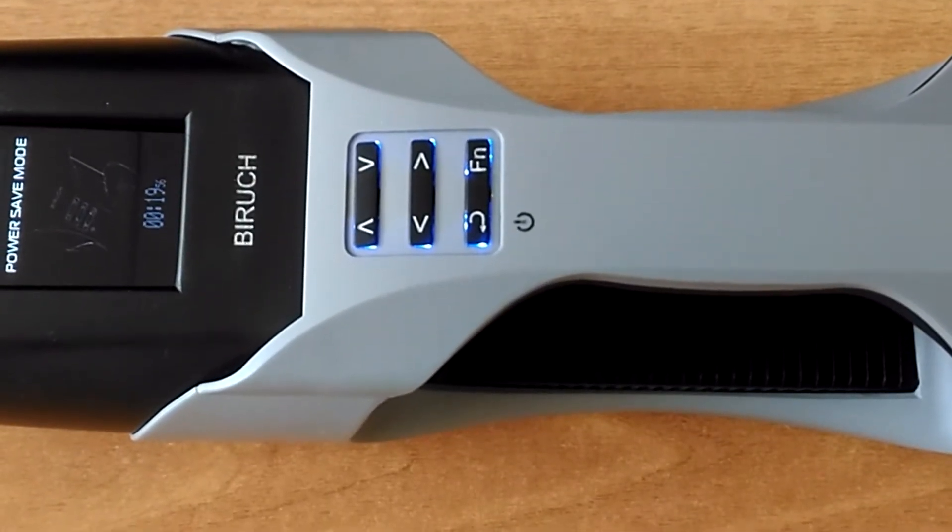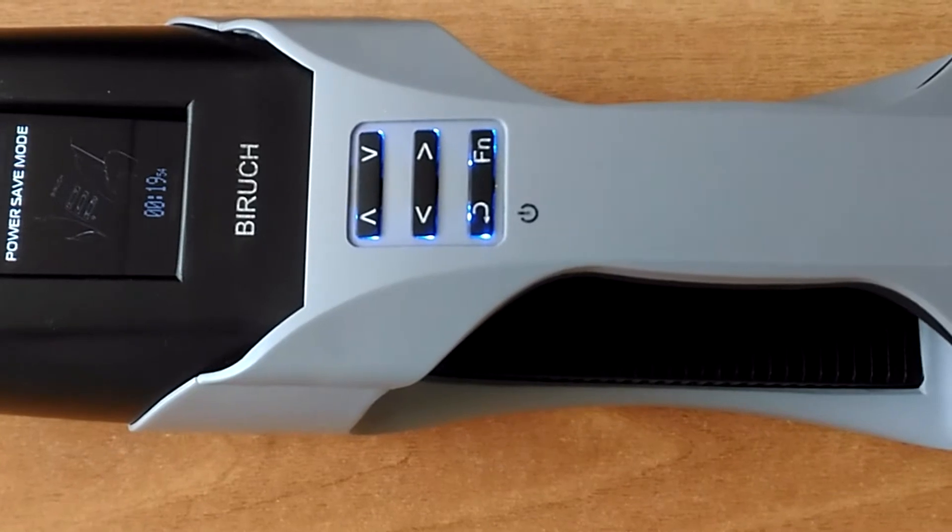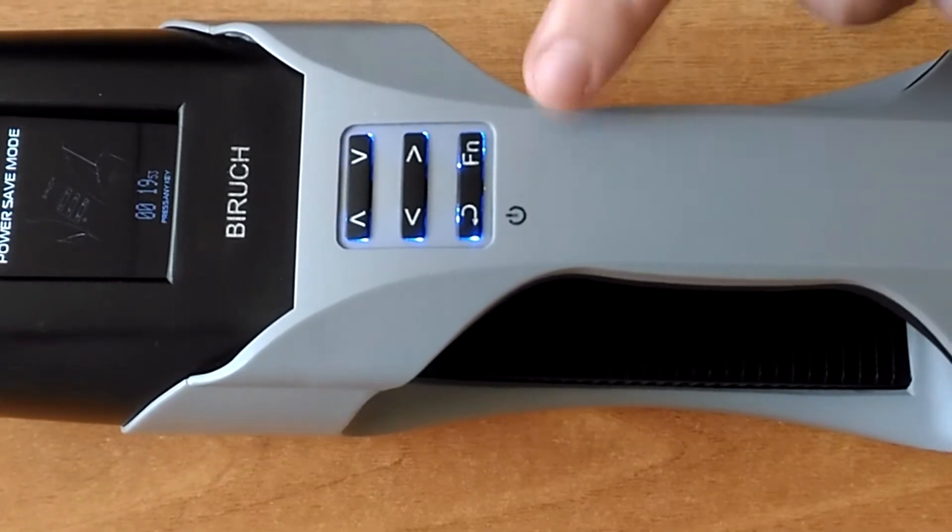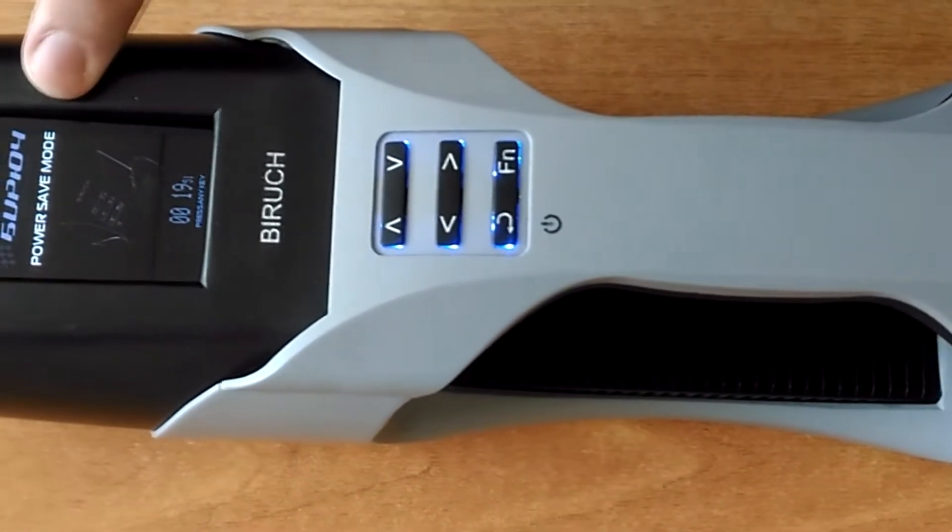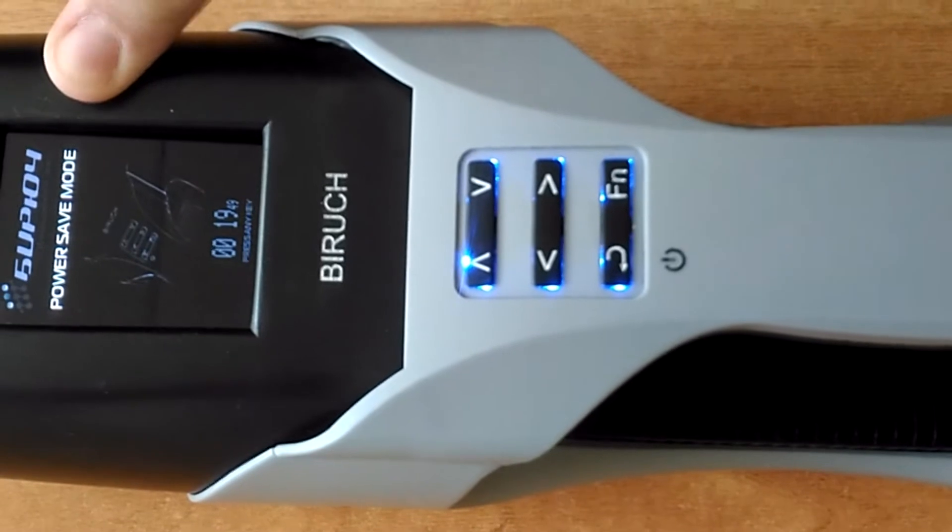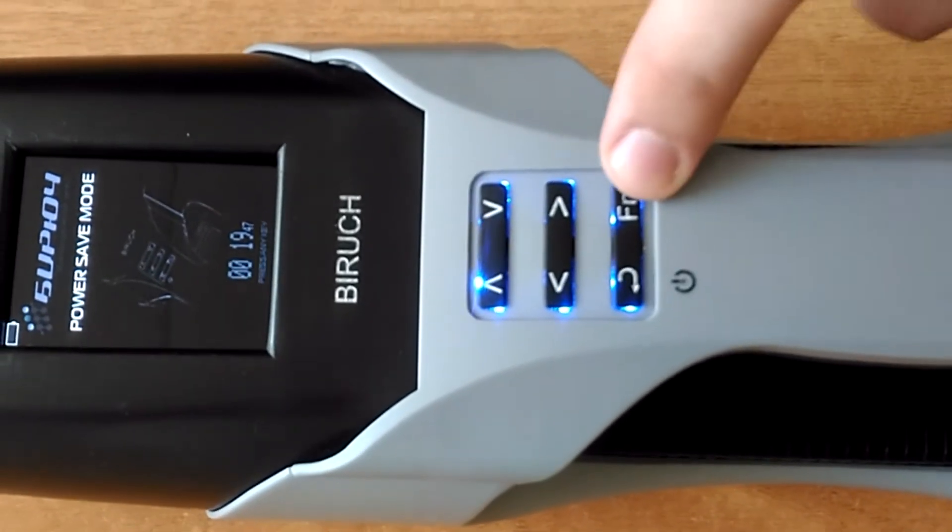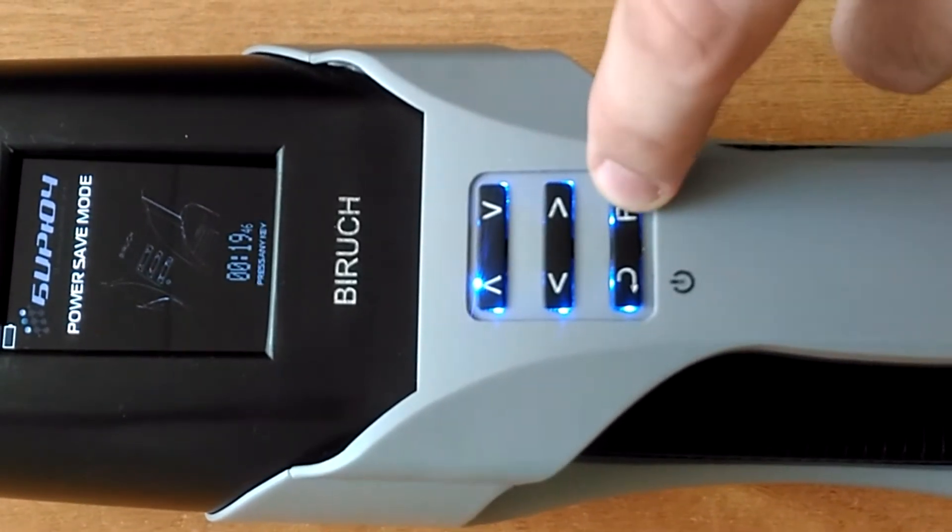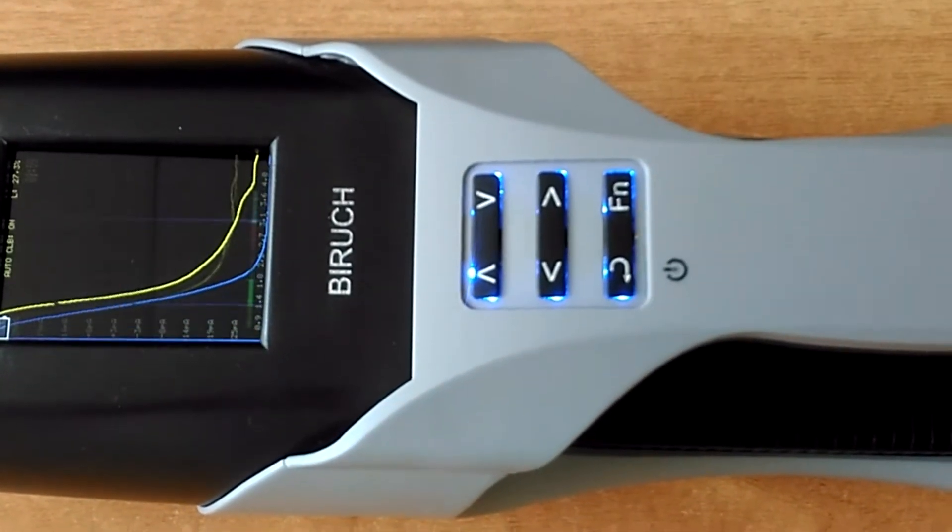The detector automatically enters the standby mode after a certain period of inactivity. The adjustable countdown timer until automatic turn-off is displayed on the screen. Press menu button to switch the detector to operation mode. It actually takes about 2-4 seconds.